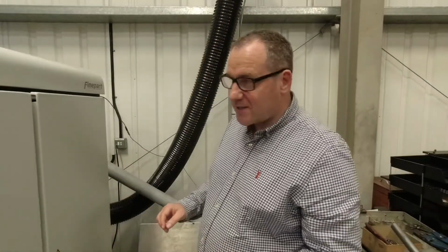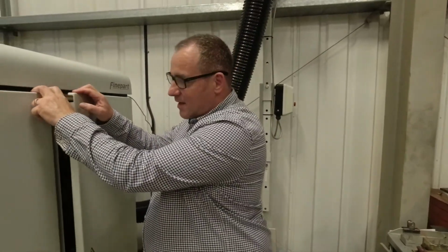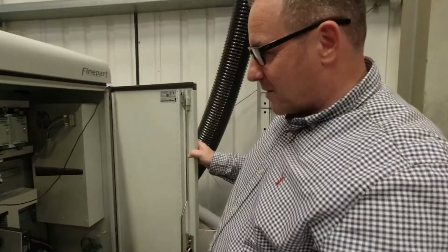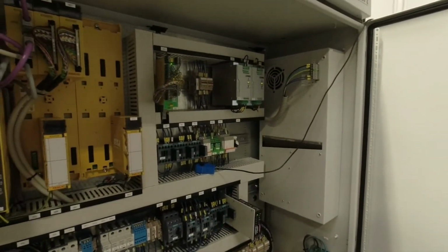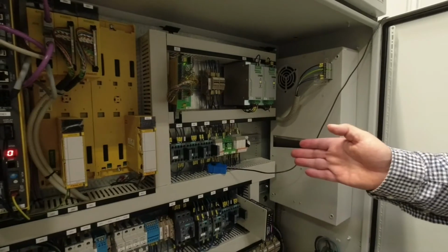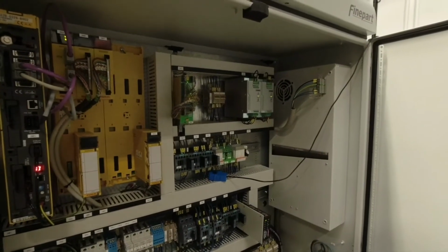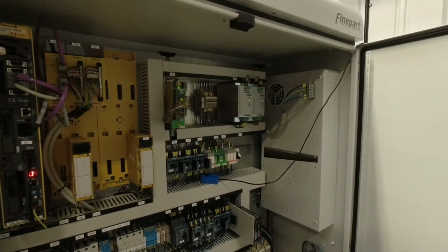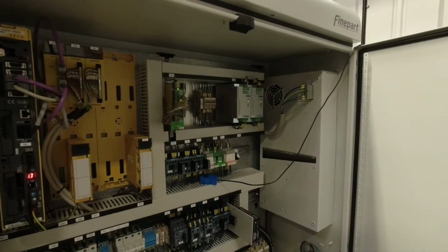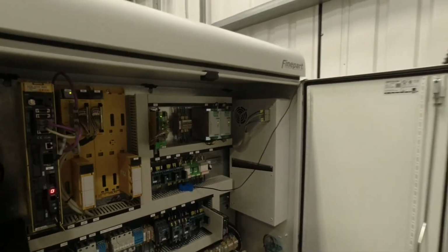Okay, today we're installing our FactoryIQ Edge device on this Finepart water jet machine. Looking in the cabinet, we've identified the feed to the solenoid for the water jet itself. We've attached our current sensor to that. That in turn is attached to our Edge device, and as soon as we power that up, it's sending data to FactoryIQ, and then we can start to correlate the data that's coming out of there with the actual jobs that are running in FactoryIQ itself.